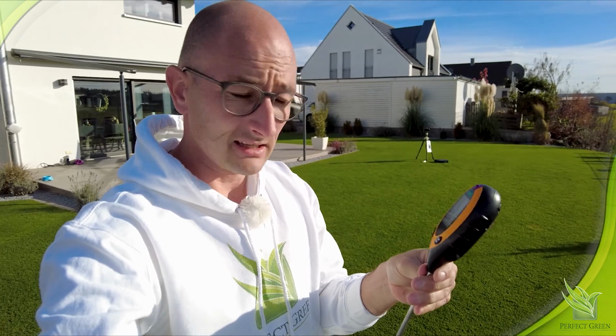I have done a counter test before I did an earth probe. It showed between 6.5 and 7, depending where I measured, and the earth analyzer showed 6.8. So in fact it works very good, and it fluctuates relatively strong. I said in the first part that the pH value fluctuates, but I still don't know if the device really works. I have no possibility to calibrate the device. The device is naturally not calibrated, and somewhere from China, clear, and as I said, it only costs a few euros. That is why I have a high performance measuring device.